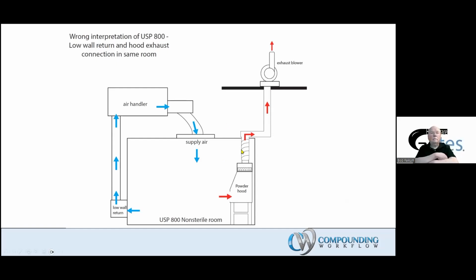But I actually saw this out in the field. A particular non-sterile compounder had a powder hood, single HEPA, sending air out of the building, but they also had a low wall return recirculating air. So notice what's happening—air comes in, partially goes out, and partially gets recirculated. Remember what I told you: the interpretation is that the C-SEC room should have one-pass air. You should not recirculate air that's been introduced into a hazardous drug room back into the air handler.